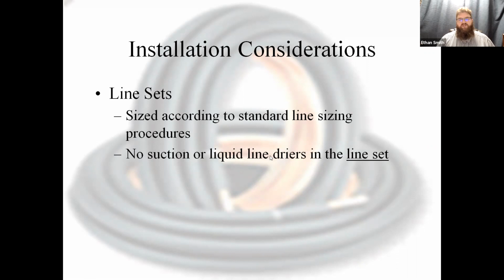No suction or liquid line dryers in the line set. This is especially true of mini splits. If you do have them, the liquid line dryers are acceptable in most cases. The reason I have this in here is I don't want it in the outdoor section. I don't want those liquid line dryers outside. It's much better if you can put those on the indoor section of the line set right before the indoor coil. That way they don't interfere quite as much and don't act as heat sinks in the heating mode.